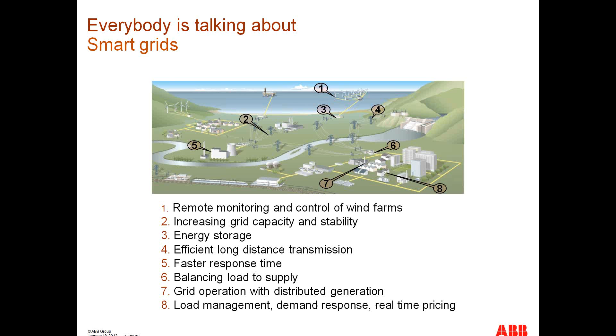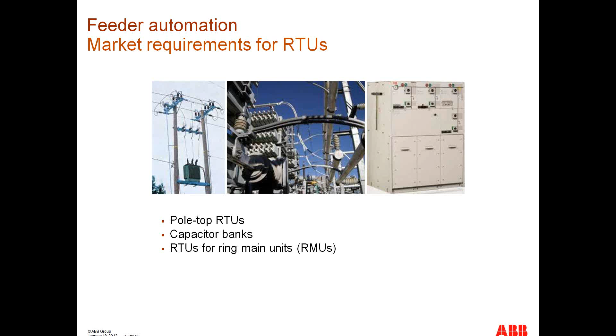After talking about smart grids, I'll say something about feeder automation. There are different fields of application: pole-top RTUs directly connected to a switch at the bay level, capacitor banks, and RTUs for ring main units, connecting the RTU in one ring, which are called RMUs.